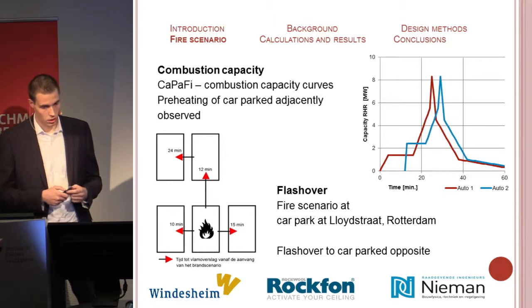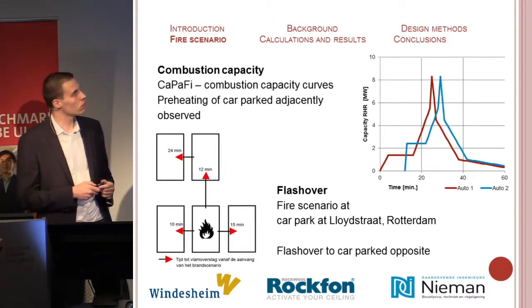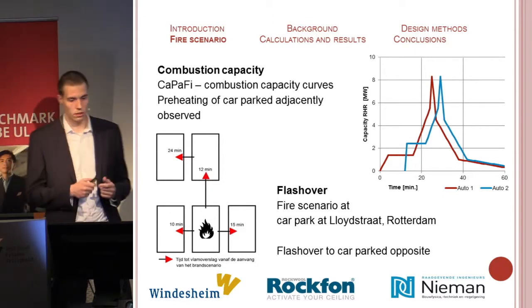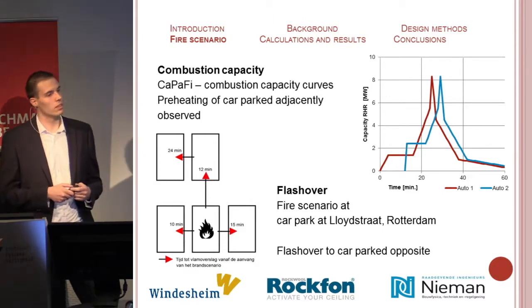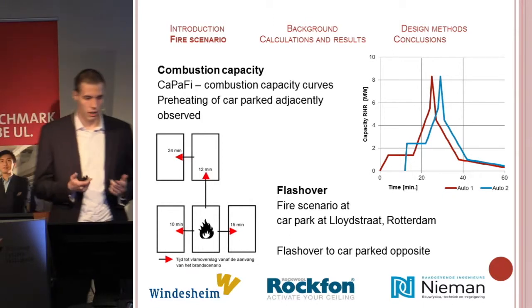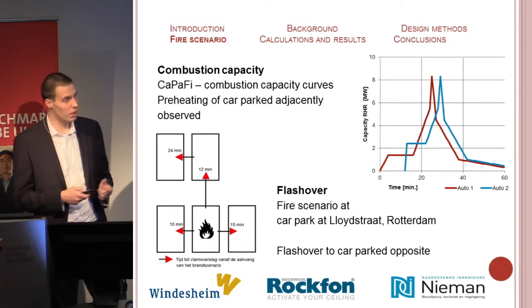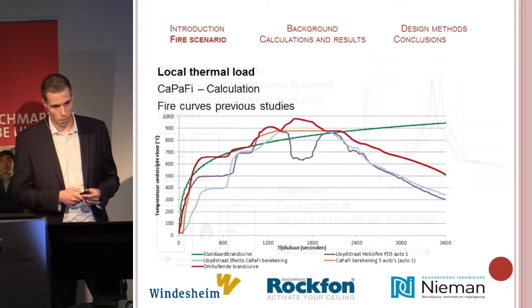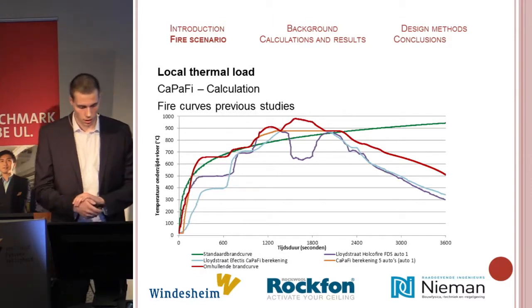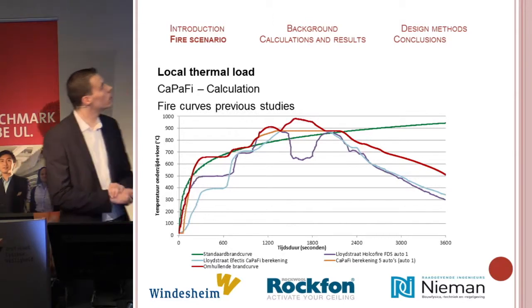The combustion capacity of a car is based on curves depicted here, and there's a phenomenon where the adjacent car preheats — the preheated car will erupt in flames sooner and faster. For flashovers, we assume the fire scenario at the Lloydstraat car park, where a flashover to cars parked opposite took place in 10 to 15 minutes. Research also confirms flashovers will occur to cars parked opposite, so this must be assumed in the decisive scenario. For the local thermal load, I used CaPaFi to plot this and compared it to results from other studies. I extrapolated the red curve, which is decisive, and applied it as the car fire curve.